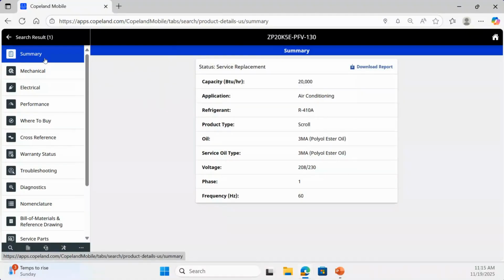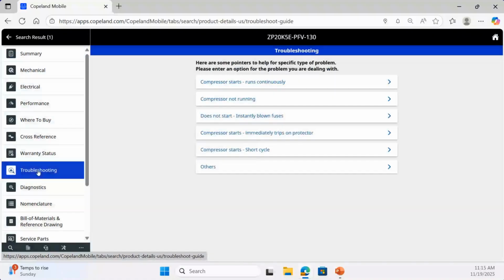So we're on this job. This compressor is installed in this residential AC system and it will not start. As you can see on the left side of the screen, you have a lot of options to choose from as far as performance, electrical, and mechanical. What we're going to do today is choose the troubleshooting tab. When we got on the job site, we knew that this compressor was not running, so we're going to start our troubleshooting with Copeland Mobile from this point.